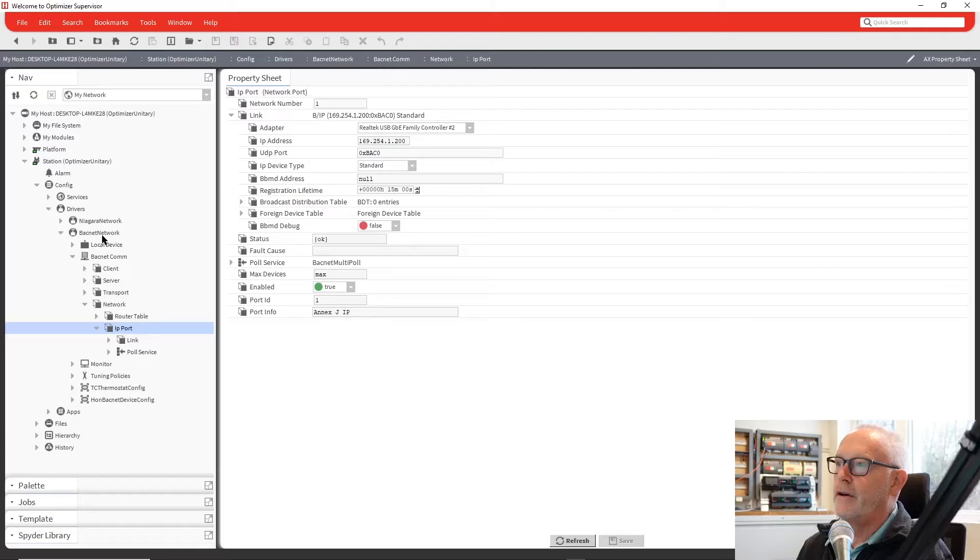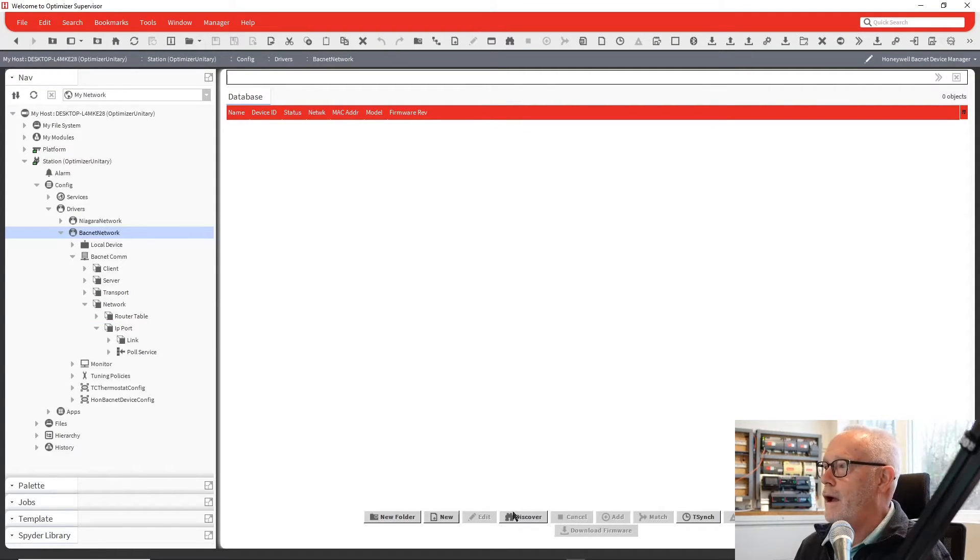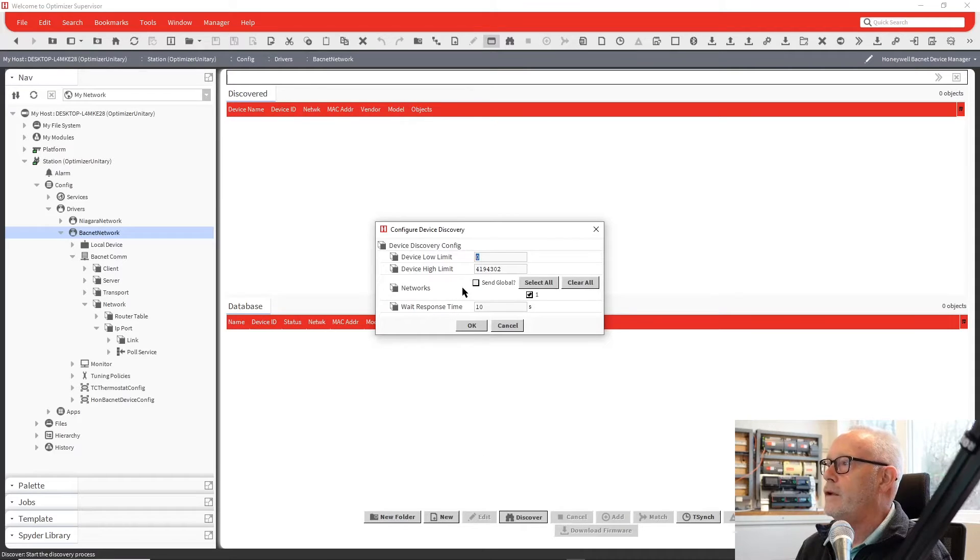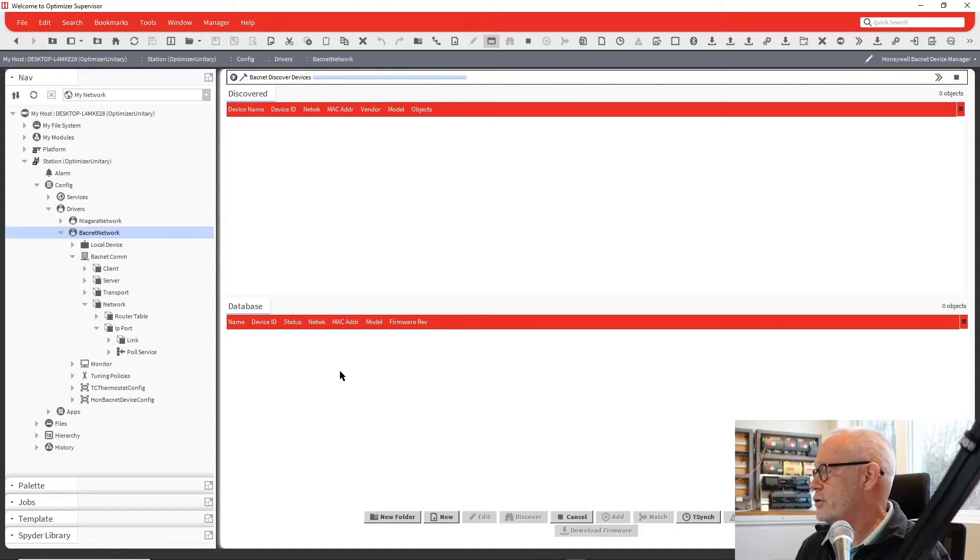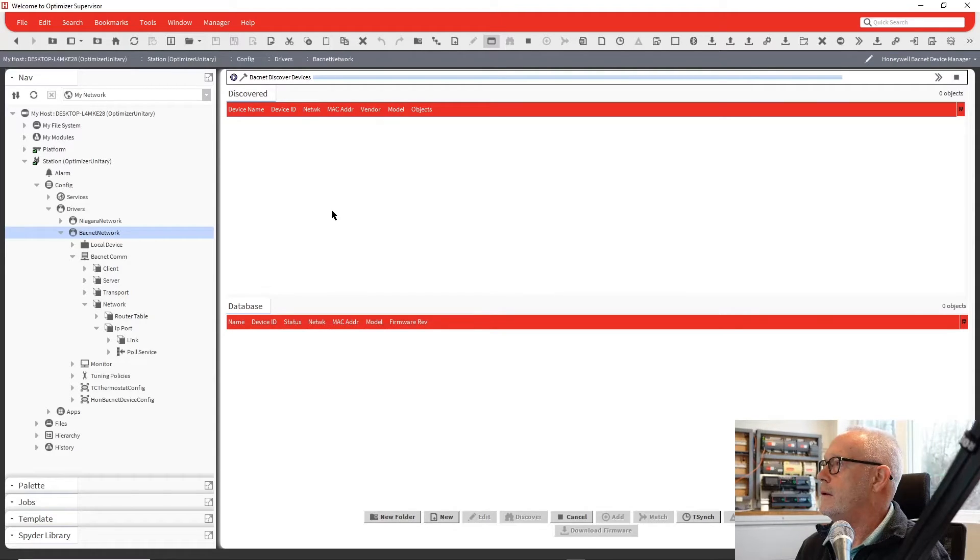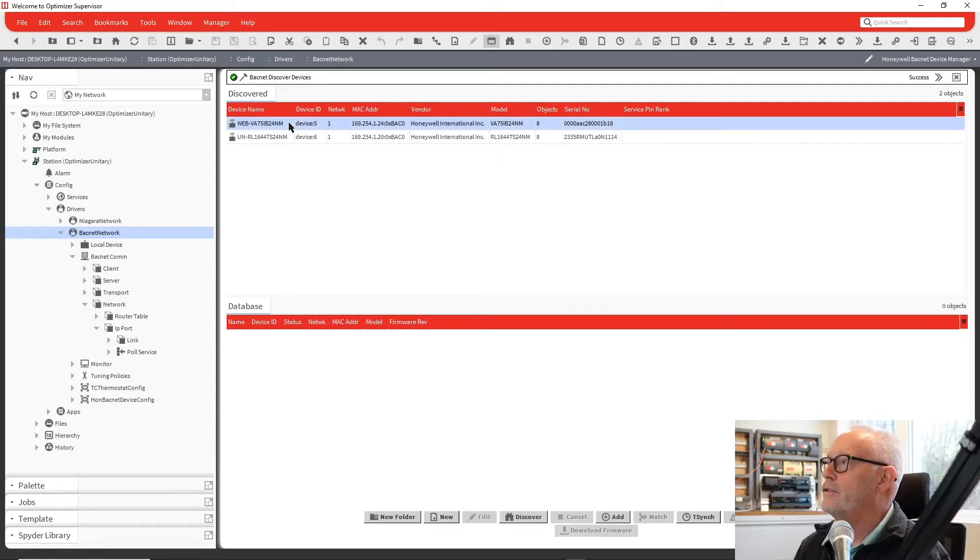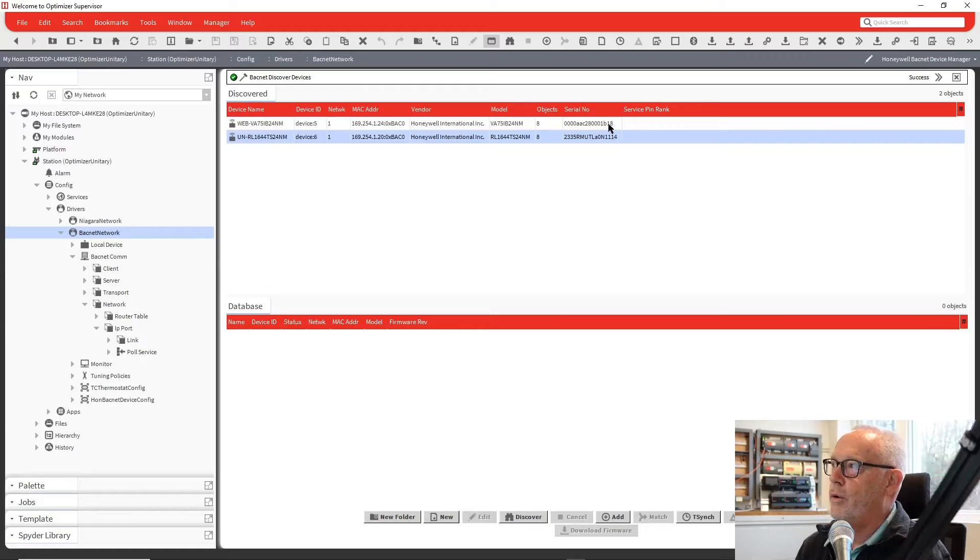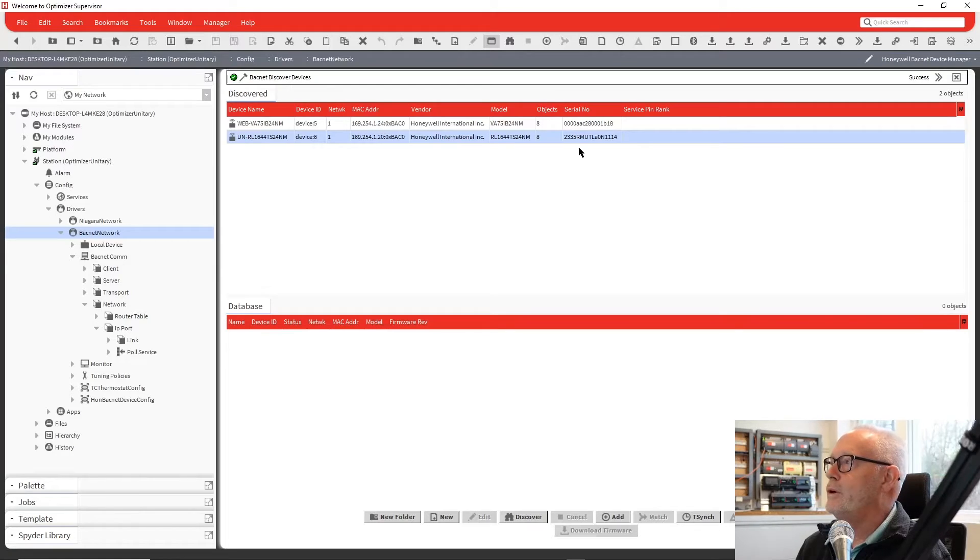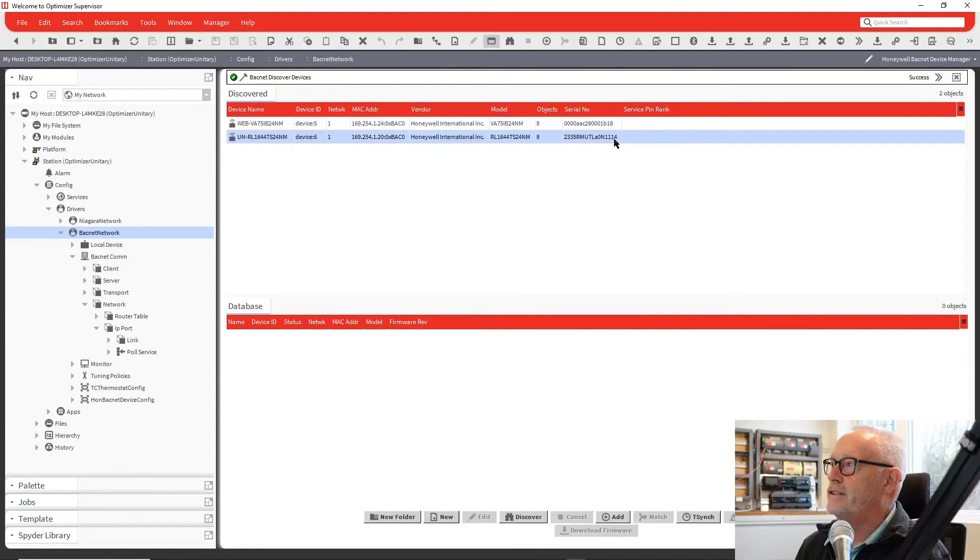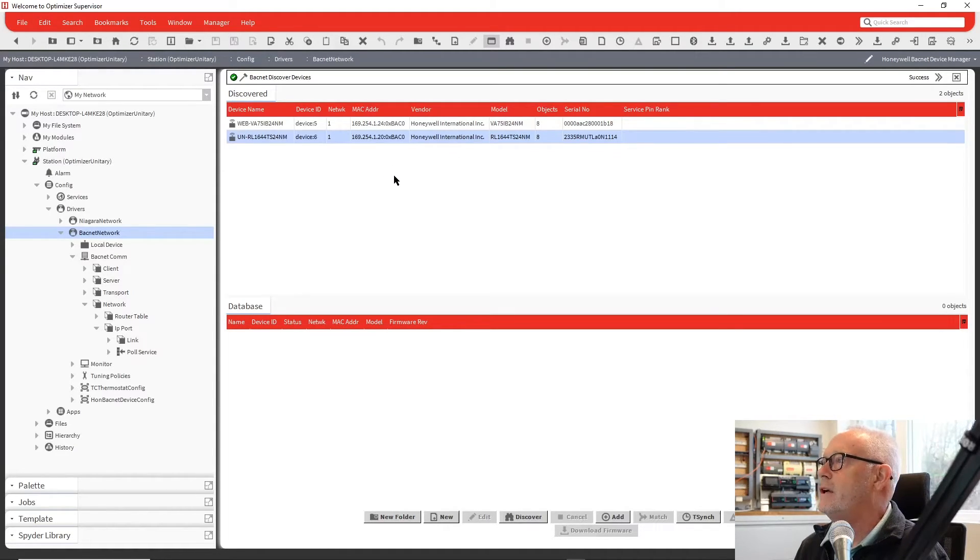So now if I go back to my device manager, I can do a discover. Go ahead and discover. My network number is 1 for IP. And we should find a VAV controller and a unitary controller in there. And they came up. And you'll see here our IP addressing. You'll see where our serial numbers are. So you can see the 18. I converted that from hex to decimal. That's where we came up with the 24. The 14 here in hexadecimal, and we converted that to decimal, and that came up as 20. And that's exactly what those IP addresses came in as.